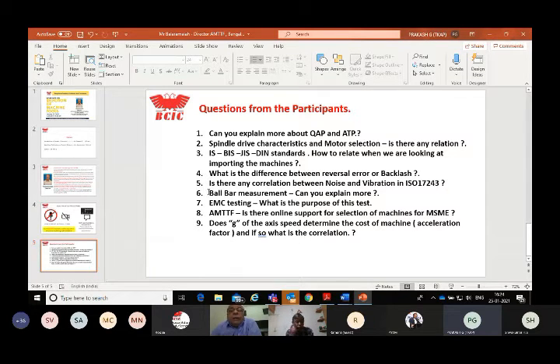Then you touched upon ball bar measurement. This is only to find out the interpolation accuracy of two moving axes, or two or more axes. It could be two linear, one linear and one rotary, or two linear and one rotary, depending on the application. It gives the accuracy of movements. If I get a 10 micron ball bar circularity or whatever error I'm trying to measure, when you machine it, you won't get less than this, it's always more, because the cutting process is also involved.